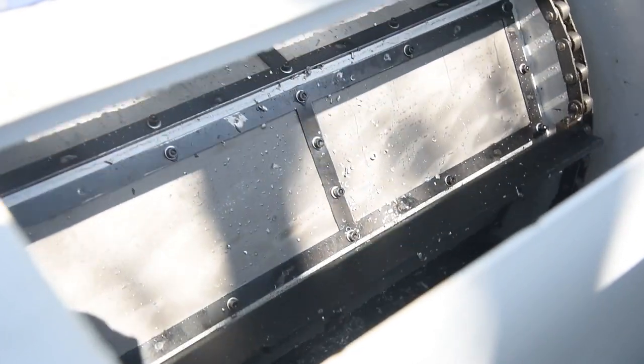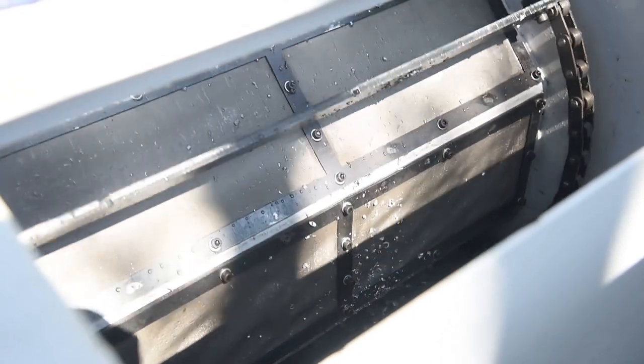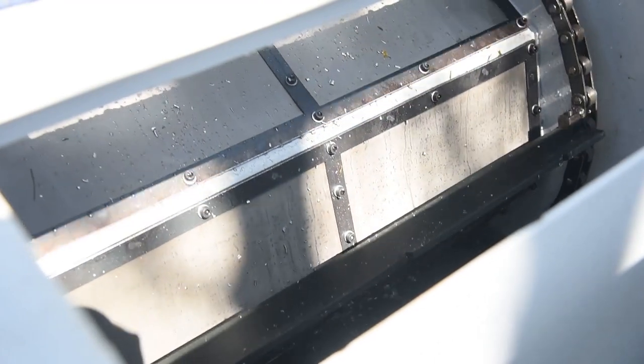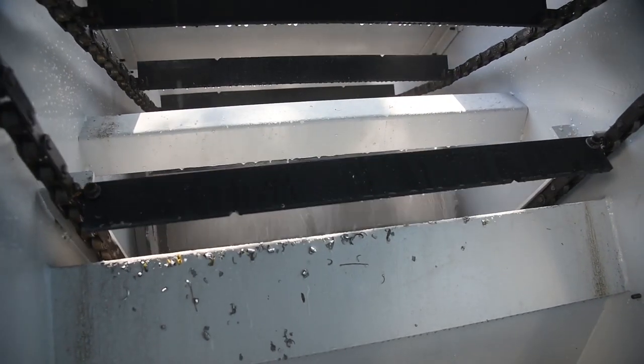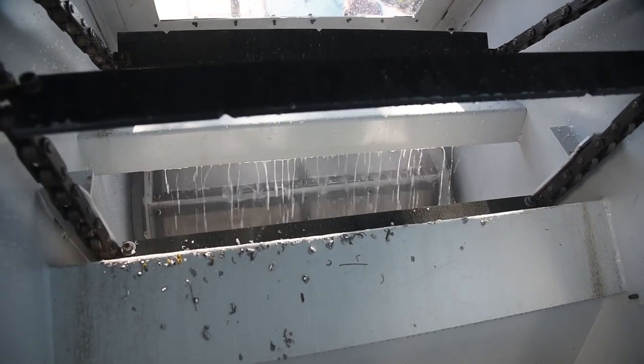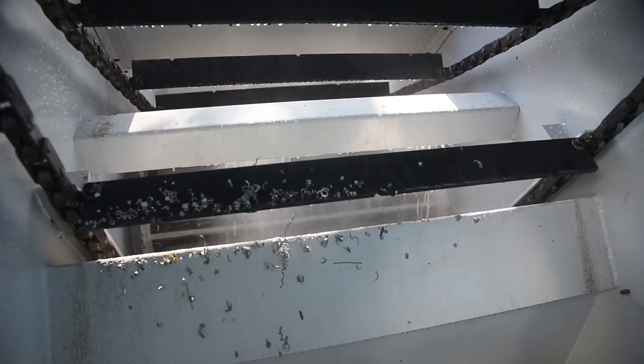Now let's see how this system works. Coolant with aluminum chips is pumped inside the system from the top. Inside the system is a continuously rotating drum with eight plates with a 30 micron mesh on top of it. Coolant passes through the openings in the mesh while the aluminum chips are trapped by the mesh. Inside the drum is a nozzle arrangement which sprays clean coolant which removes the chips trapped by the mesh.